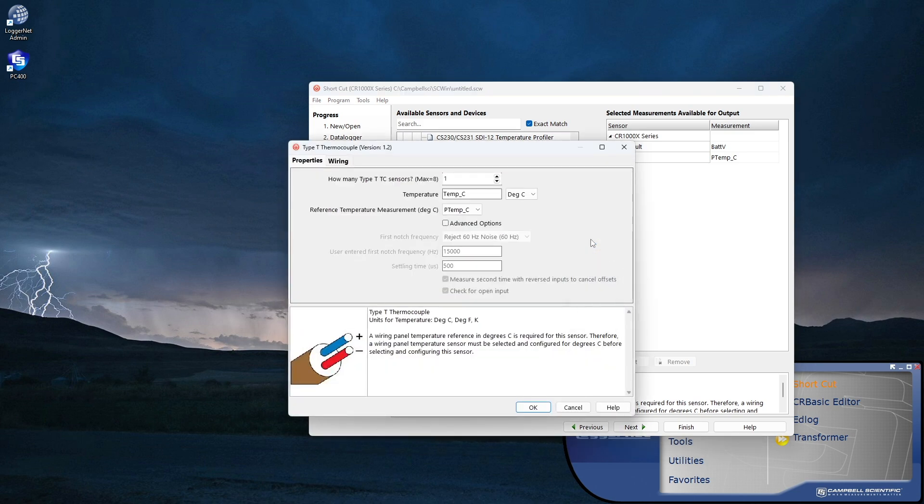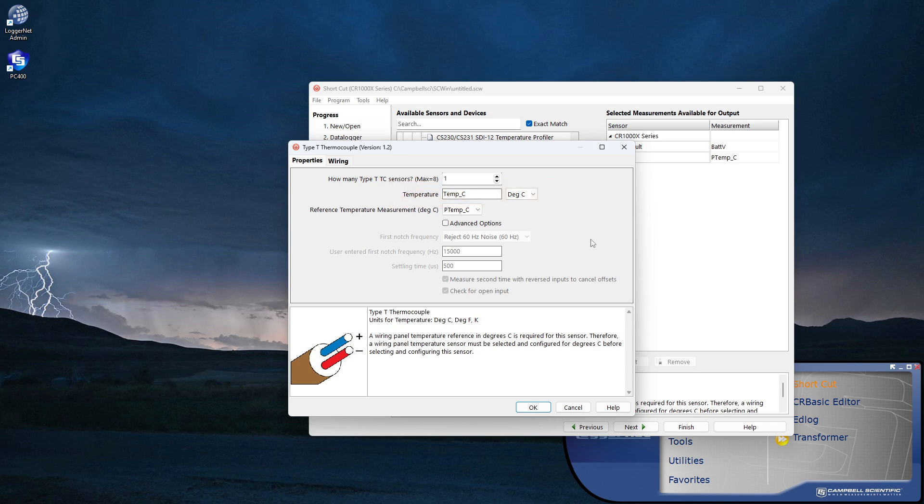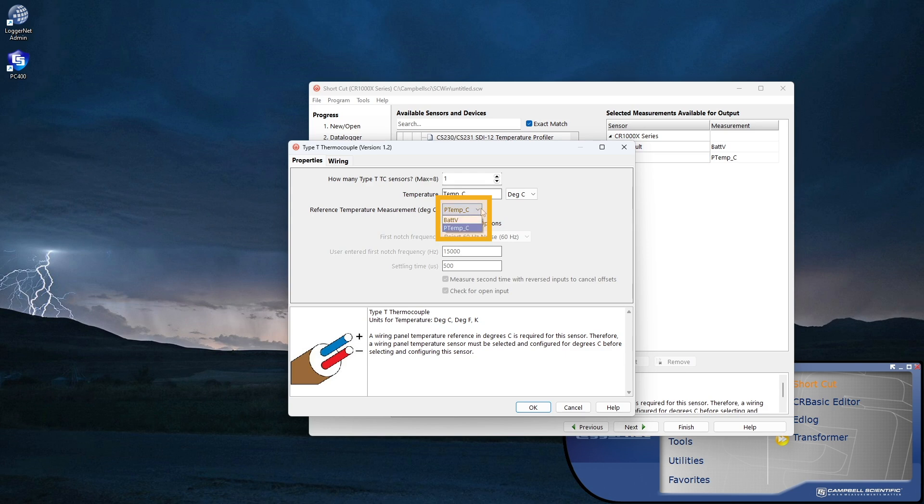I will use the default settings. If I wanted to change the name of the variable that stores the temperature measurement, I would change it here. Thermocouples require a reference temperature. For this tutorial, I'll be using the CR1000XE wiring panel temperature, PTEMP-C, as my reference.